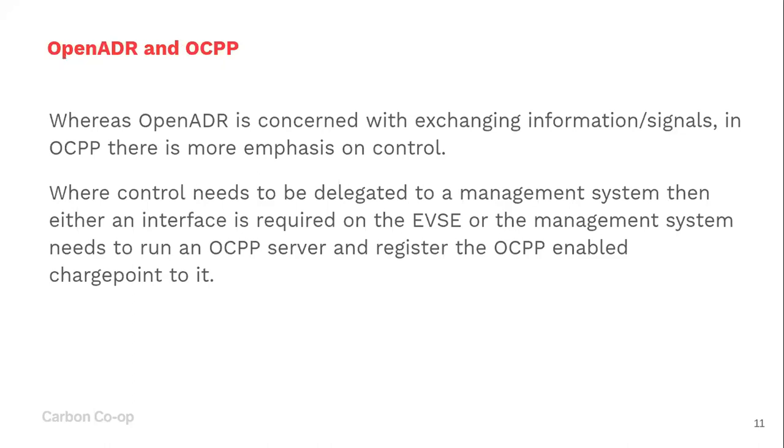Whereas OpenADR was mainly concerned with the exchange of information and signals about demand-side response events, in OCPP there is certainly more of an emphasis on the control of the EV charger and the EV itself. But in the use case we're looking at, where the control needs to be delegated to a management system in the home or the business, then some sort of interface is required to the charger. The option is either to talk OCPP to the charger or there needs to be some alternative interface available, and this inevitably leads to needing to implement some sort of OCPP server on the management system itself in order to talk OCPP to the charger.